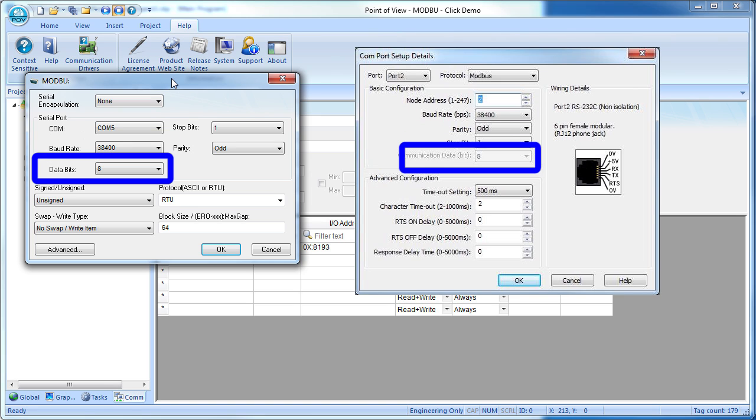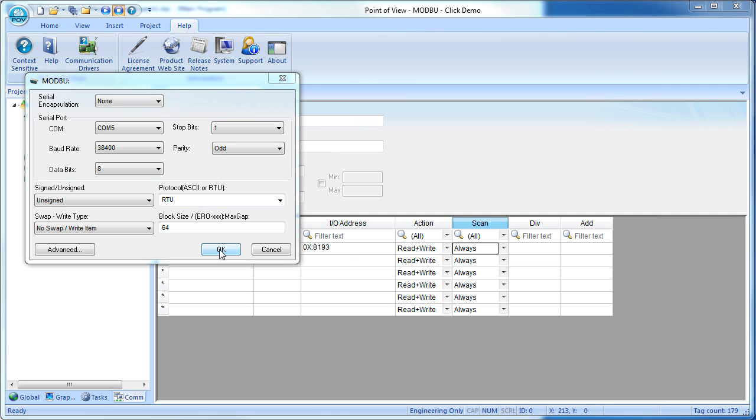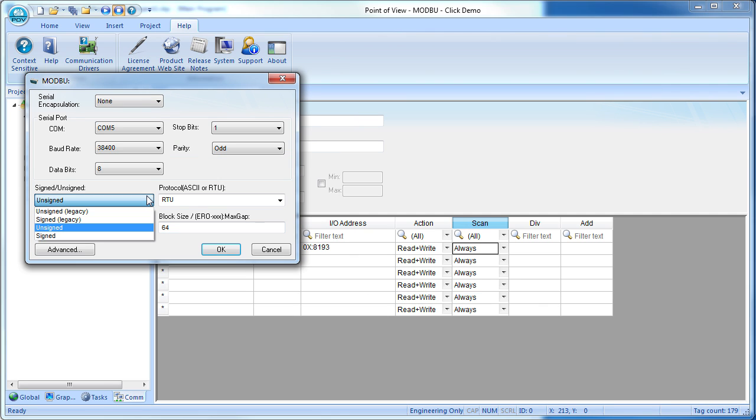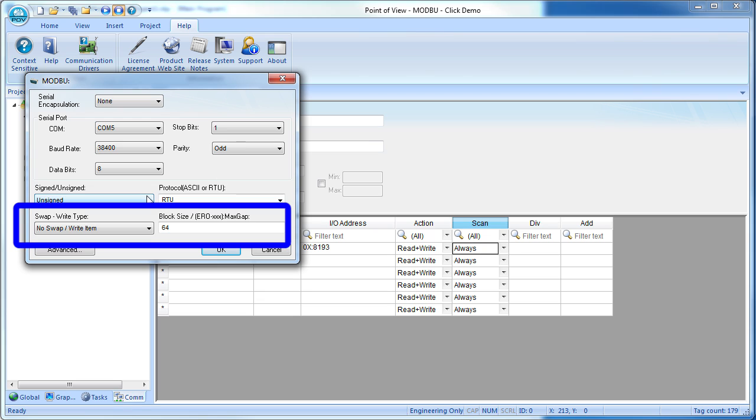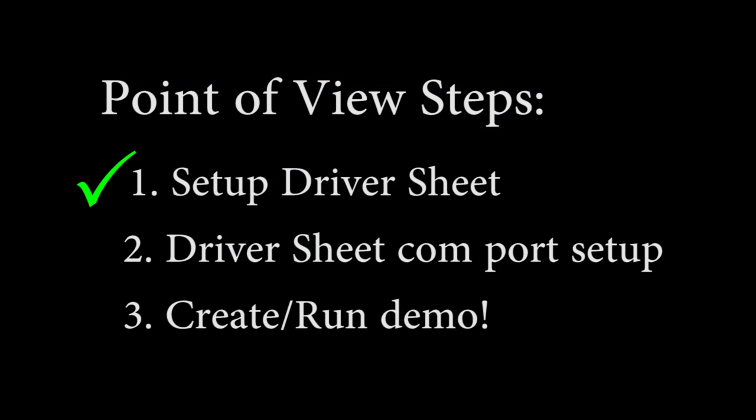and parity are all the same as what's on the Click PLC. We are using a discrete I/O bit in this example, so signed and unsigned doesn't matter, and we are using Modbus RTU. If you need to swap bytes or change the block size, do that here. Great, that takes care of step 2.